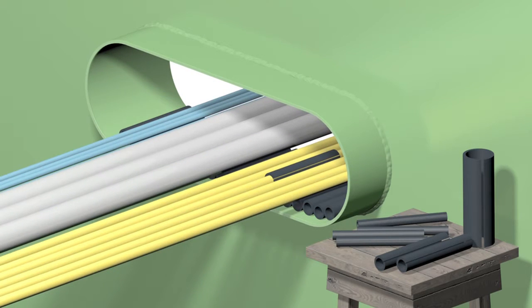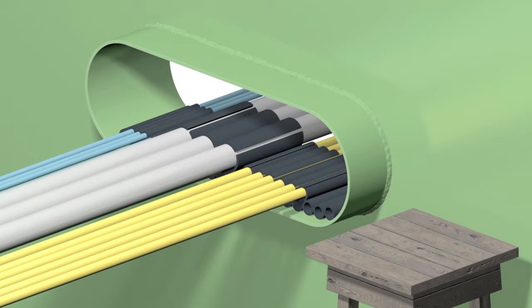Positioning the insert sleeves in the middle of the conduit leaves a free space of 20 mm at the front and the back for applying the sealant later on. Be accurate from the beginning on, especially with higher filling rates, it might be difficult to correct afterwards.